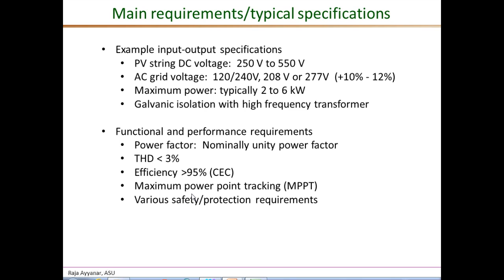Another key function that is required of all PV inverters is maximum power point tracking. As the environmental conditions change, the inverter should continuously adjust the effective impedance seen by the PV panels in order to continuously draw the maximum possible power from the sun. There are many different MPPT algorithms, and in some of the later videos, we will look at a few popular MPPT methods.